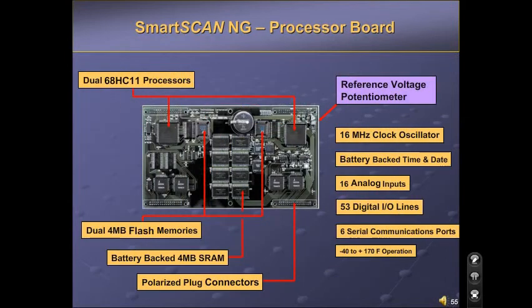This is the 2300-100 EPCC board. This is the main processing board of the system. Each processor controls different functions of the system. The reader processor monitors train activity, alarms, talker messaging, and system integrity. The COM processor controls the serial ports and communication to modems and polling systems.